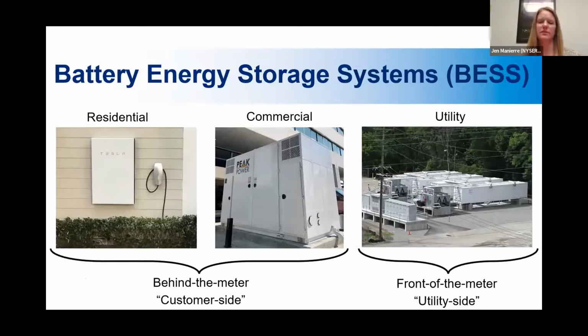There are a couple different ways that these systems will interconnect, right? So we have the smaller residential and commercial systems, which are typically associated with a building whose load they're serving. A residential battery energy storage system is going to push power back into the home that it's attached to when that energy is needed. Same is true for a commercial system. And we'd refer to both of those as behind the meter or on the customer side, because they have this direct tie to a meter that's serving a specific building and a specific load. And that's how they're treated in the electricity markets, without going into too much detail.